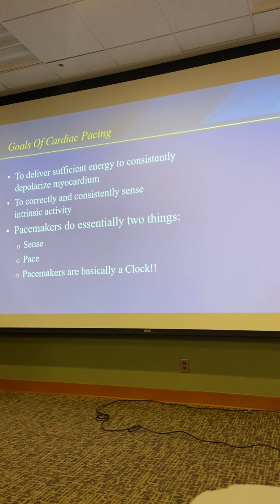So, the idea here is that it's going to deliver enough electrical energy to depolarize the heart. It's going to correctly sense the activity that's going on in the heart so it can make some good decisions about which beats need to be provided and which ones don't. Essentially, the pacemaker is responsible for two things. It's to sense electrical activity that's intrinsic to the heart and to provide what's missing. It's a clock. It's set like an alarm clock for a second from now, and if it doesn't see an intrinsic beat, it provides a paced beat, and if it does see one, it'll skip. It's more complicated.